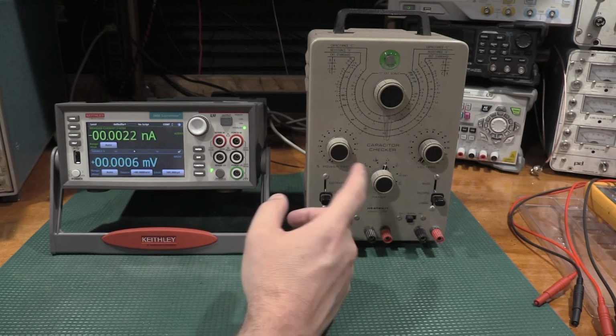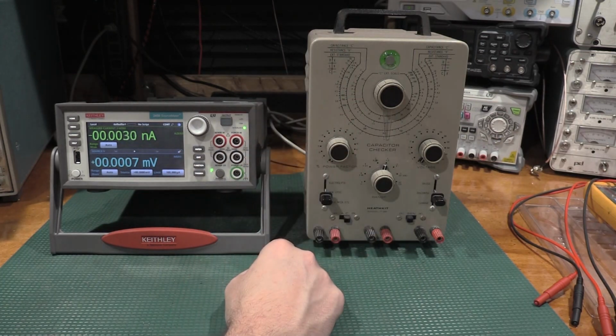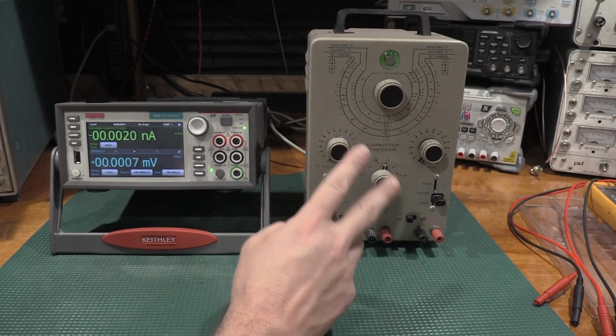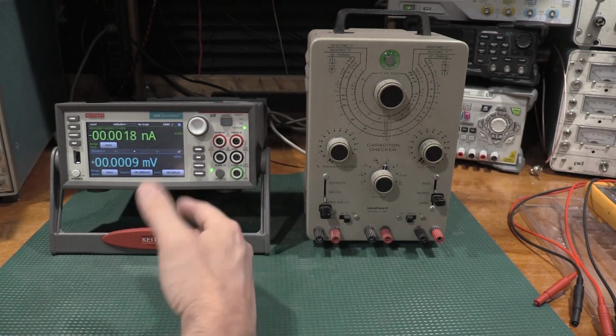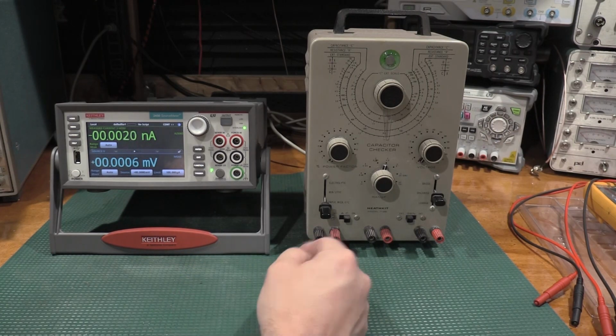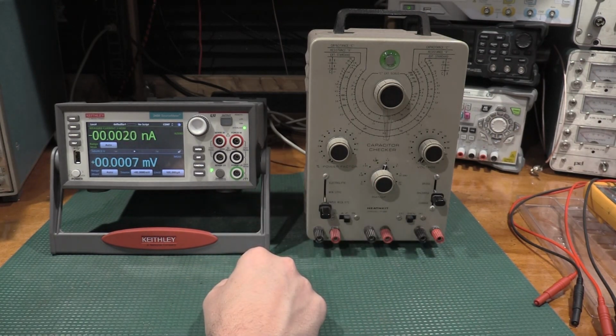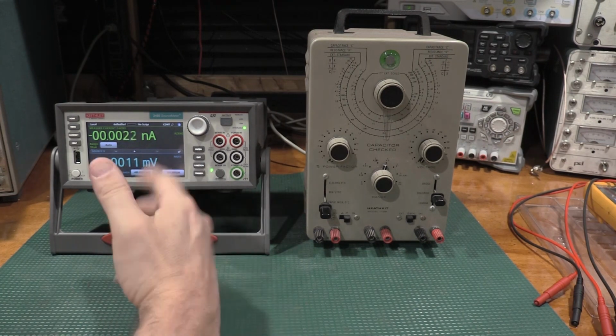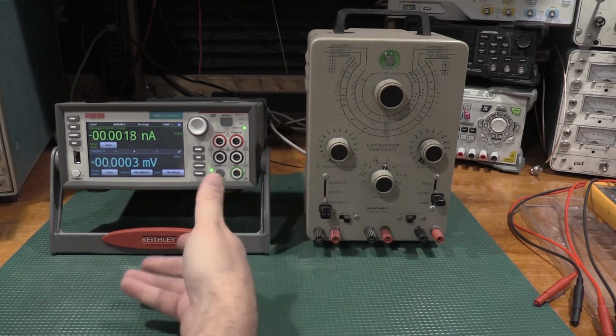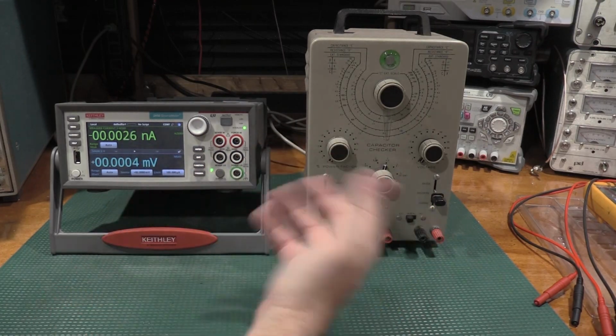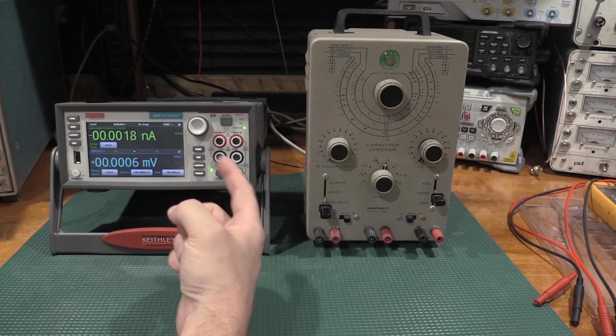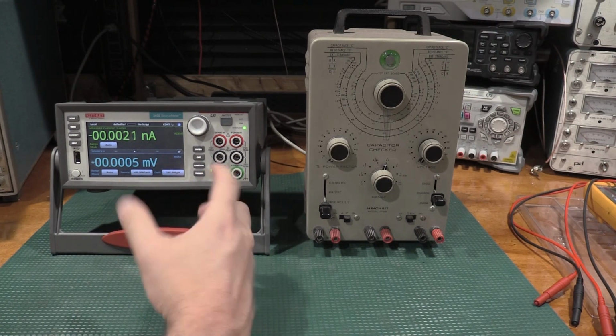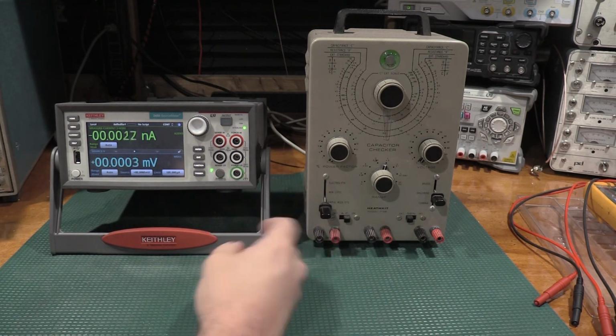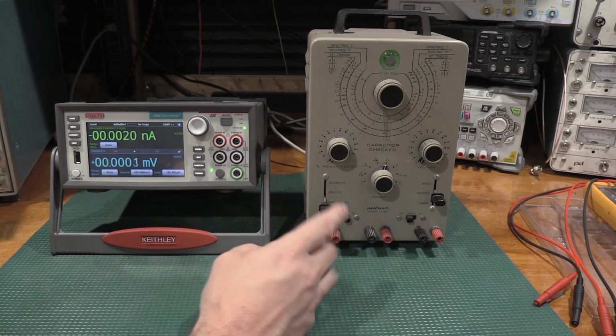The mini lytic is 5 microamps. Will open the eye and it'll be a passing grade. And the paper and mica is 2 microamps and it'll be a passing grade. That's what you adjust the 3 resistors in here for when you're doing that. On this unit, I can set what I want the passing grade to be, and it can do pass-fail testing and things like that. I can say if it leaks higher than X, it fails, or it passes. So that's all settable in the UI for the SMU. And I also have much better measurement capabilities because this only goes down to about 2 microamps.